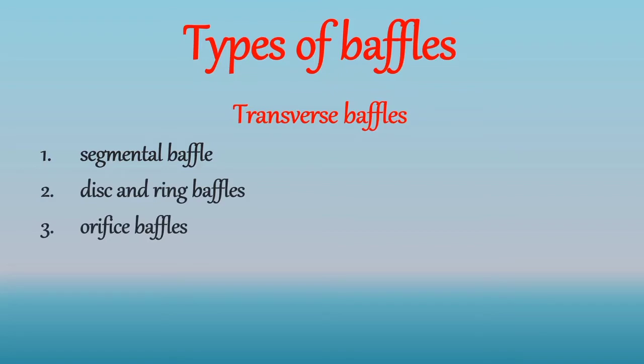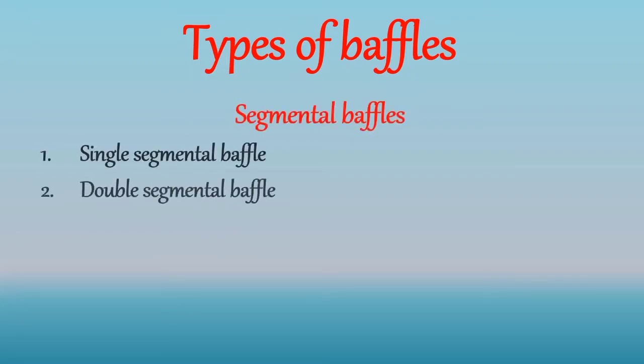Out of these, segmental baffles are most commonly used. There are mostly three types of segmental baffle: single segmental, double segmental, and triple segmental baffle. Out of these, single and double segmental baffles are most frequently used because they divert the flow most effectively across the tubes, and hence they provide maximum heat transfer for a given pressure drop in a minimum amount of space. But what is meant by single segmental, double segmental, and triple segmental baffle?